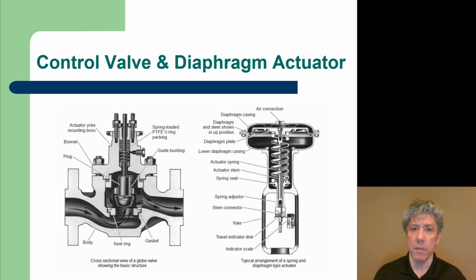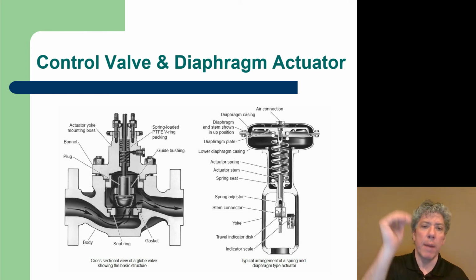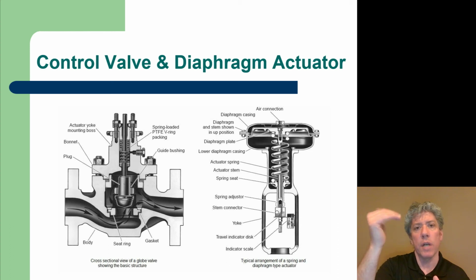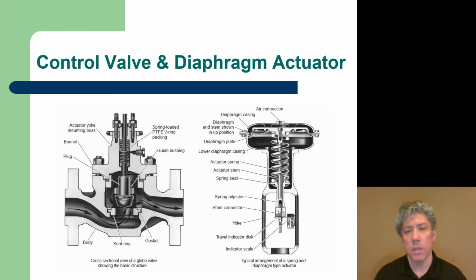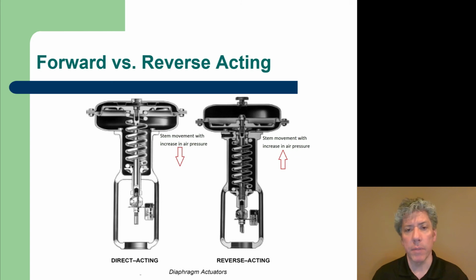But there is still significant friction, so you end up with a lot of hysteresis in this type of setup, where if you're trying to have the diaphragm actuator change direction, say you're opening the valve by pulling the plug out to allow more flow and you change directions, well, you may still be at essentially the same pressure, but you have to overcome friction going the opposite direction, because now you have static friction to overcome, and so you have to increase the pressure beyond where you were to get a different valve setting. So there's typically a lot of hysteresis in this type of device. You have to somehow overcome that.